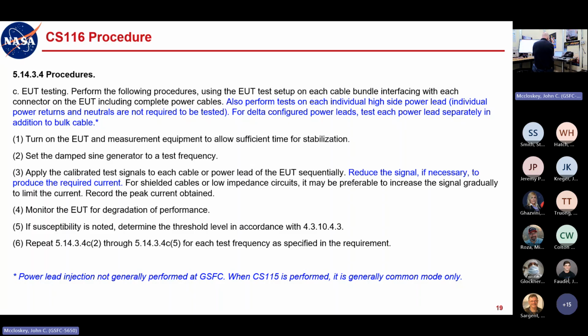So this actually tells you reduce the signal level to get to the required current. That's just something to note: if your pre-calibrated level is not giving you the required current, that means the impedance of your loop is now higher, so it's limiting the current. There's no statement saying increase the signal to get the desired current. Don't do that. That's how you can stress and damage things. But if you're getting higher than the pre-calibrated current, then it says you can reduce the signal to get the desired current.